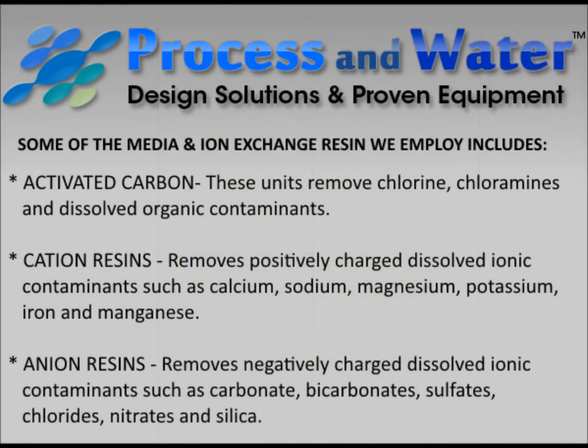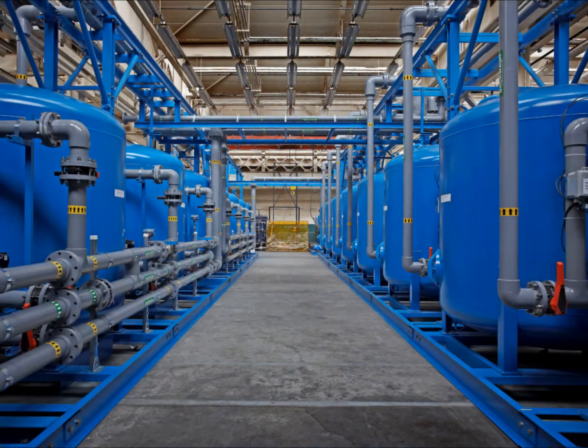Anion resins remove negatively charged, dissolved ionic contaminants such as carbonate, bicarbonates, sulfates, chlorides, nitrates, and silica. The anion resins used offer stability against osmotic, thermal, and impact shock.